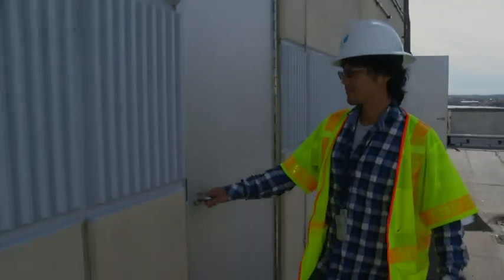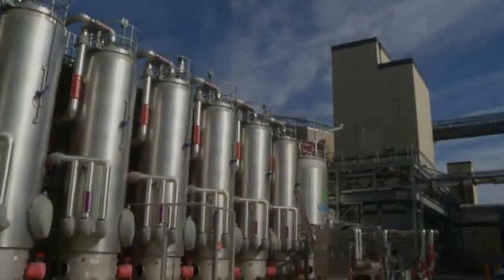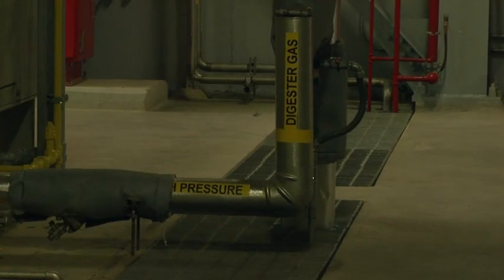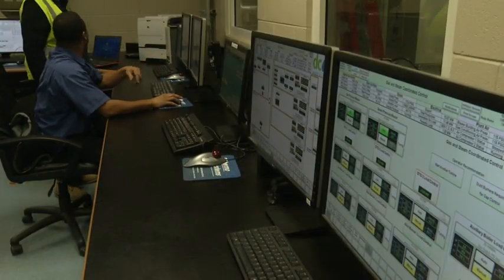The process begins inside this room. Water is extracted from the solid waste. Engineer Ryu Suzuki supervises the operation. We thickened it up to about toothpaste consistency. The sludge is then pumped into a row of tanks that cook it at high heat. Microbes then break down the organic matter, producing methane gas, which powers these giant turbines, generating one-third of D.C. Water's power.